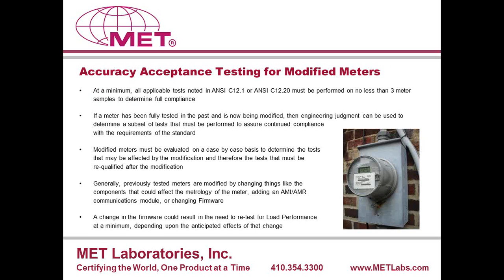The acceptance testing for modified meters, we talked about. I talked about it some earlier. Anytime there's a change to the product after the original compliance, you want to make sure that you're bouncing the question off of us. This is what we changed. How does it affect it? We feel it may affect this, or we feel it does not affect the meter because... That's the type of communication that would go between MET and the manufacturer, and we come to a consensus using engineering judgment on what may or may not affect previous compliance testing. If there are tests that need to be run, some subset of tests from the original suite of compliance tests, 3 samples would need to go through at a minimum. Same as the standard. We try to follow exactly what the standard requires for all test cases.